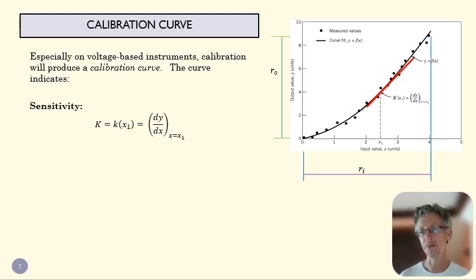So let's say we have a load cell, which measures force. I might have force values down here, one newton, two newtons, three newtons, four newtons. And this over here is going to be in voltage that tells me, okay, once I apply three newtons of force to my load cell, it's going to read roughly six volts. That tells us a lot, that takes that transduced voltage and then tells us, oh, this is what that actually represents. The sensitivity is the slope. The red line here.